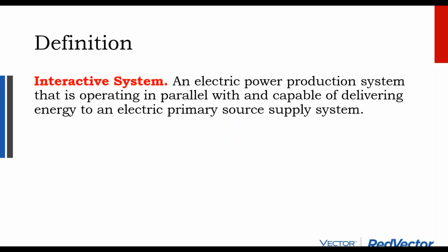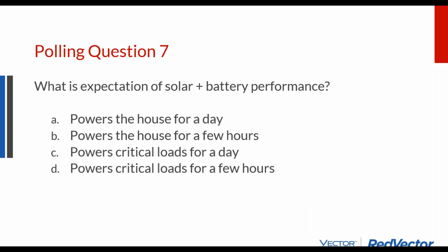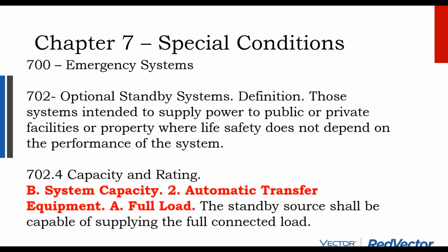So now we're getting into special systems. In the interest of time, we're gonna talk about the main important ones here. The first is transferring loads. So we have standby loads must be capable of supplying the full connected load for an automatic transfer switch.